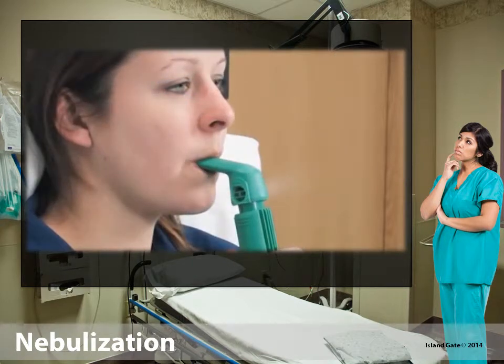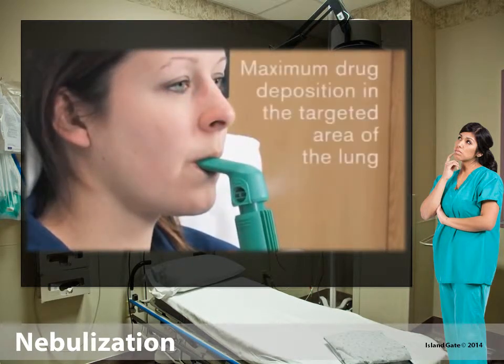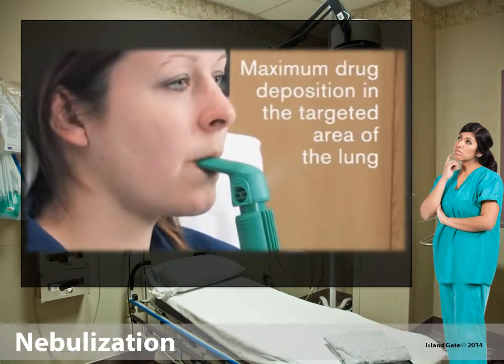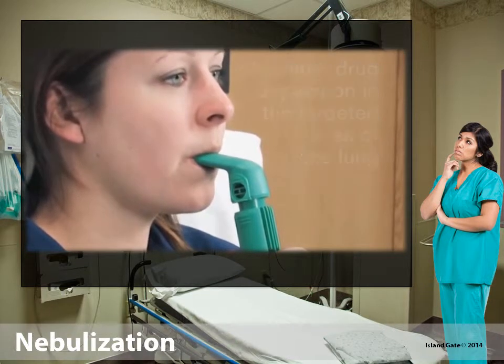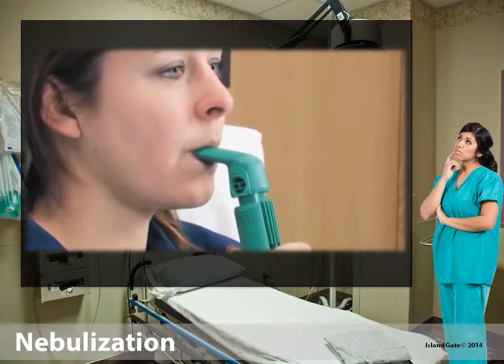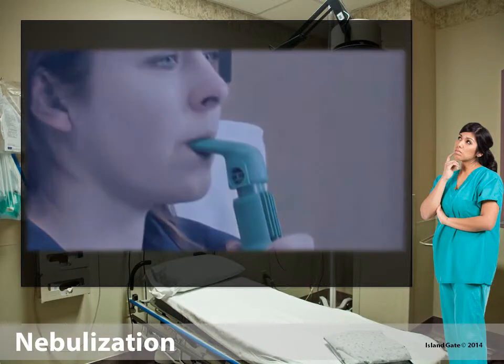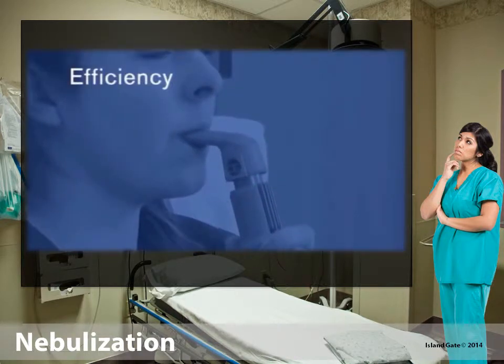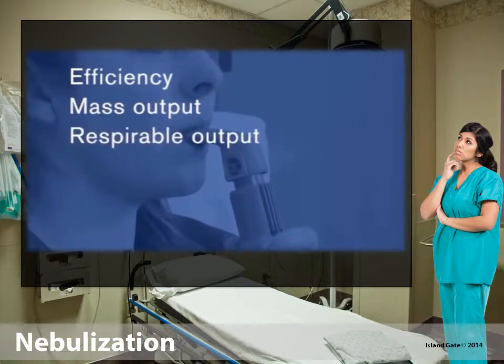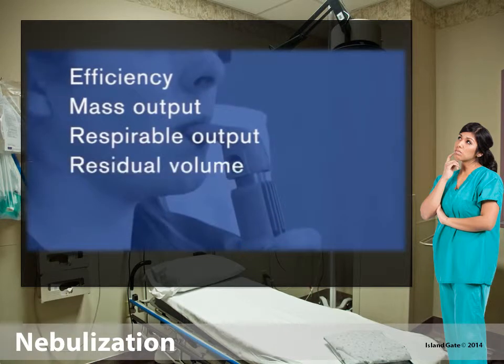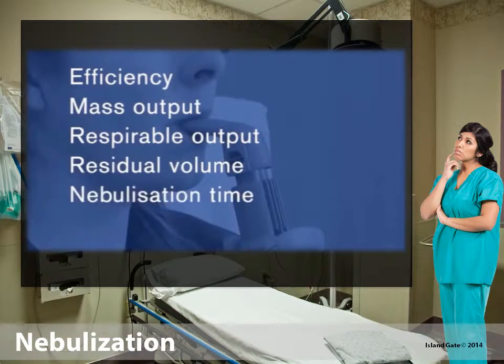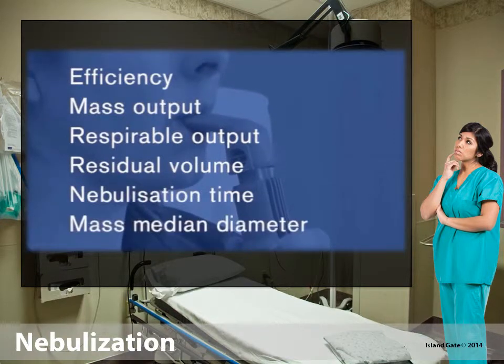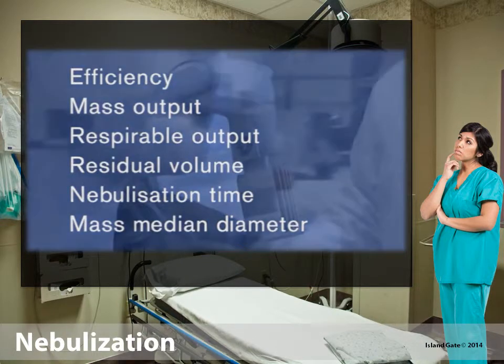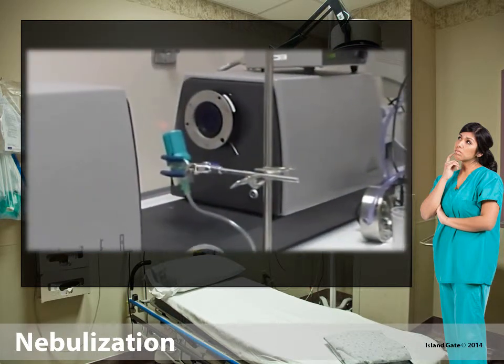What we require in a nebulizer is maximum drug deposition in the targeted area of the lung. To judge how a nebulizer performs, we can look at these factors: efficiency, mass output, respirable output, residual volume, nebulization time, mass median diameter. With these values, we can determine how well a nebulizer performs.